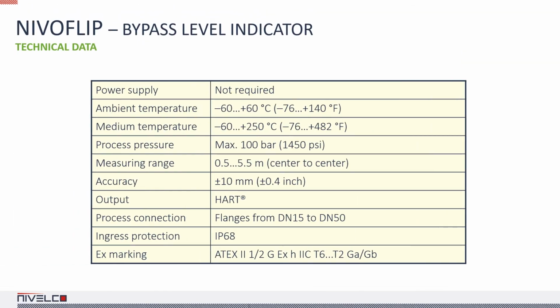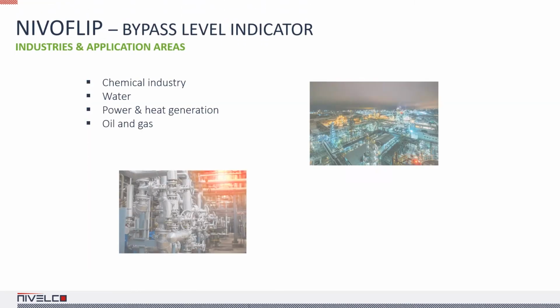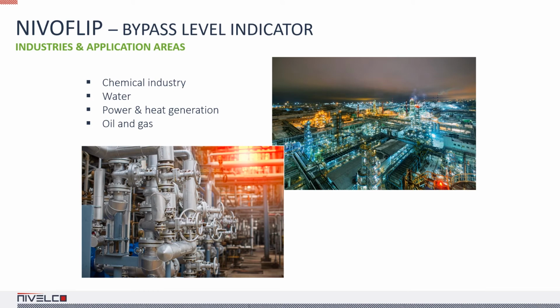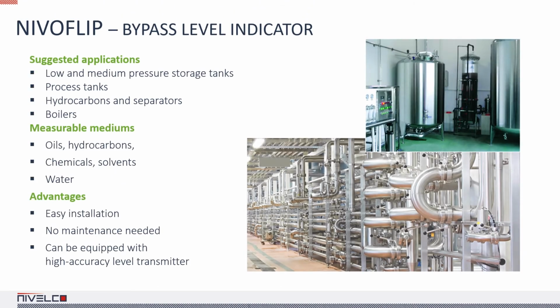The NIVOFlip is EX certified, and it is NIVELCO's only level measuring device that doesn't require a power supply. The typical application areas are the chemical industry, water processing, power and heat generation, and the oil and gas industry. The suggested applications are low and medium pressure storage tanks, process tanks, hydrocarbons and separators, and boilers. The medium must be homogeneous. The device is easy to install, it is maintenance-free, and it can be equipped with a highly accurate level transmitter.